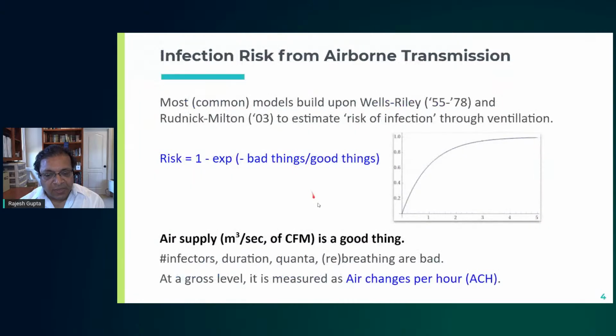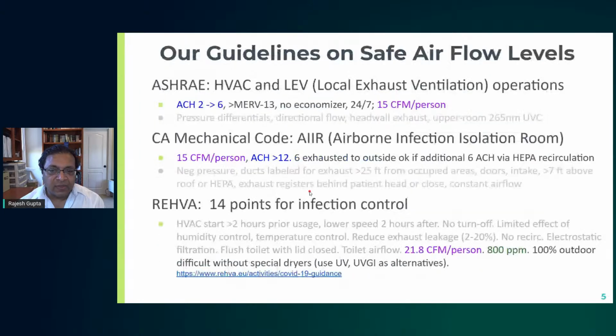So there have been a number of guidance documents from standards bodies that tell us what the airflow should be. For example, ASHRAE, which is a North American standard, has come back with a recommendation that a normally designed building with ACH 2 or 3 should be increased to ACH 6, for example, and they should use filters of a certain kind and try to maintain an airflow per person of 15 cubic feet per minute. In the case of hospitals, there's a much stricter standard. For example, maintaining air handling air change to be 12 per hour, 12 changes per hour.